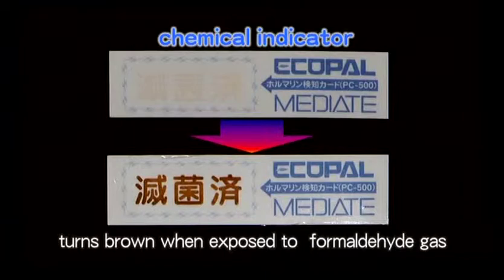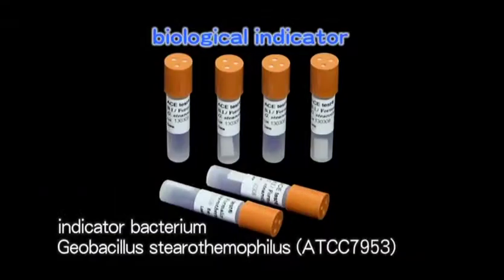We have our exclusive chemical indicator, which turns brown when exposed to formaldehyde gas. Our biological indicator uses a special bacterium and monitors the effects of sterilization by checking the change of color after incubating the bacterium for 24 hours in temperatures ranging from 55 to 60 degrees Celsius.